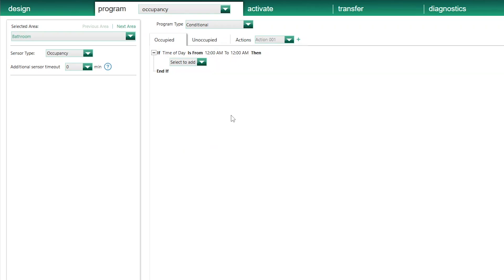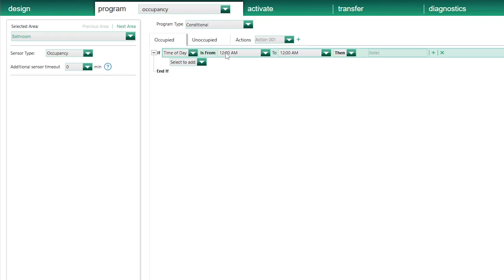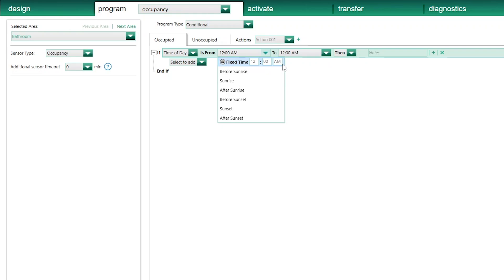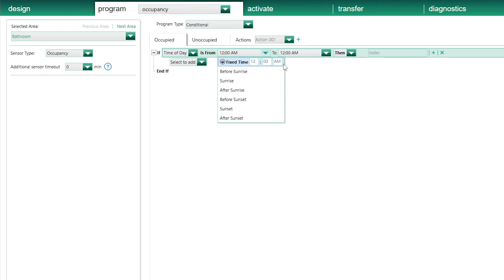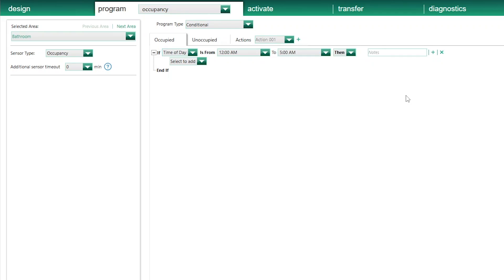If Time of Day is from — and here I have multiple options — I can select a fixed time like 12 a.m. midnight, or I can make use of the built-in astronomical time clock that resides in any Lutron Homeworks processor to create my starting point based on sunset and sunrise time, which changes every day. In our example today, I'm going to set it from midnight, 12 a.m., to 5 a.m. Then I'll add the action I want to trigger during this period of time.